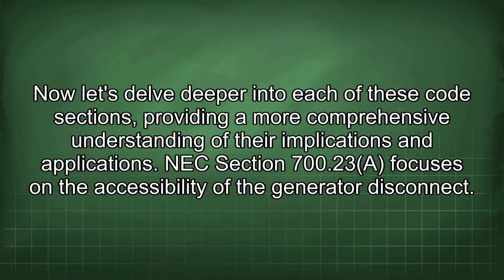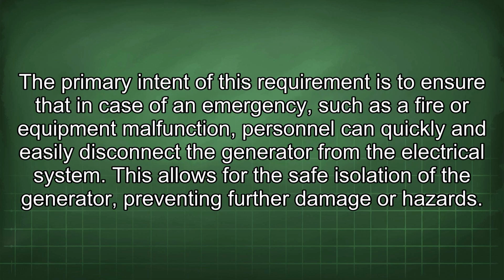Now let's delve deeper into each of these code sections, providing a more comprehensive understanding of their implications and applications. NEC section 700.23 focuses on the accessibility of the generator disconnect. The primary intent of this requirement is to ensure that in case of an emergency, such as a fire or equipment malfunction, personnel can quickly and easily disconnect the generator from the electrical system. This allows for the safe isolation of the generator, preventing further damage or hazards.